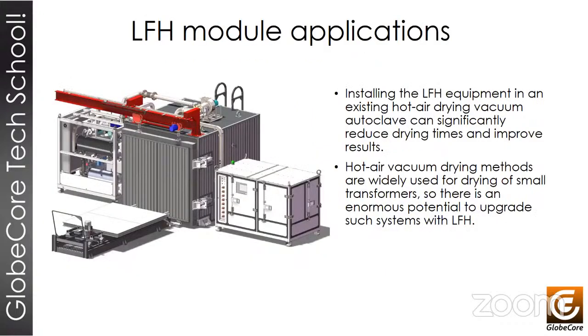A hot air drying vacuum chamber in combination with the LFH system will yield the result. This method of drying distribution transformers ensures minimum energy costs and offers other advantages, such as an accelerated drying process, high capacity, and easy control. Hot air vacuum drying methods are widely used for drying small transformers, so there is an enormous potential to upgrade such systems with LFH. A traditional hot air drying system would take at least twice as long to complete the drying process.